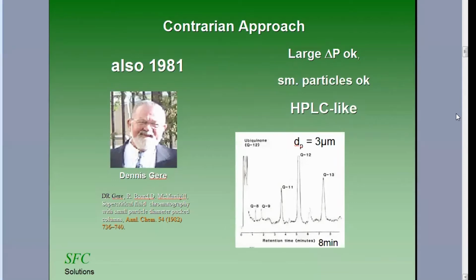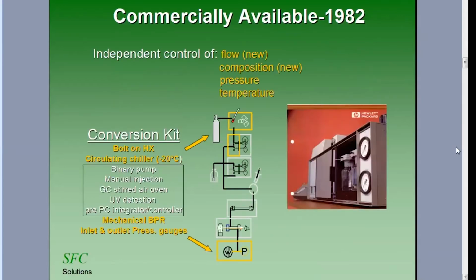An example here at the bottom is the separation of ubiquinones on a short 3-micron particle diameter column. I see it's an 8-minute run, a very simple type of chromatogram, not the complexity, not the efficiency you saw with the capillary work. What he used was a standard LC. So this was an old, early generation LC that he merely bolted a circulating chiller to cool the pump heads, and also a mechanical back pressure regulator.